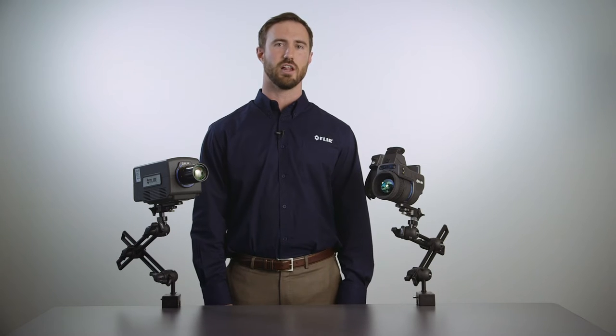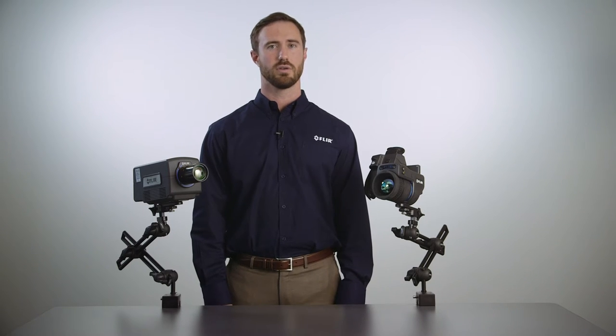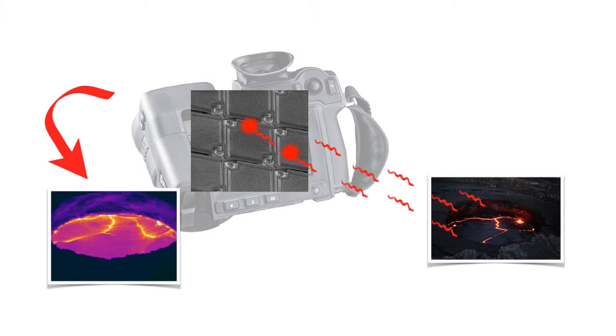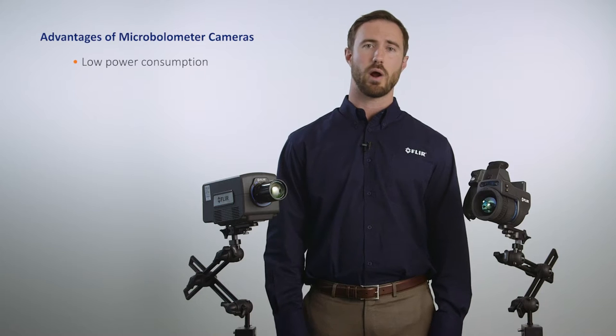The resistance change is measured for each element, converted to a digital count, calibrated to a temperature, assigned a color or grayscale value, and presented as a viewable infrared image.